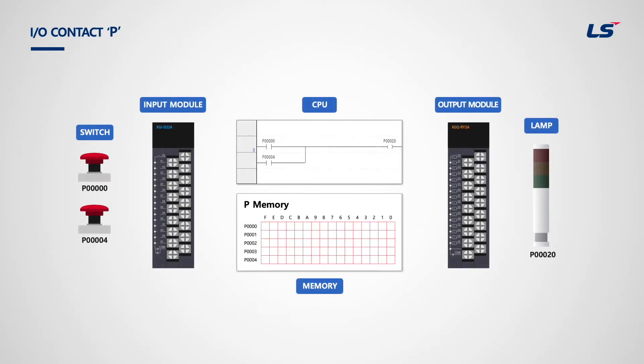Let's look at P memory. On the left there is an input module, and on the right there is an output module. If switches connected to P0 and P4 on the far left are activated, then input signals must come in. As seen in the ladder program, P0 and P4 are A contacts, and if either one of them has an input signal, then output signal P20 will be turned on. P memory is based on bit, so word P0 has 16 bits.